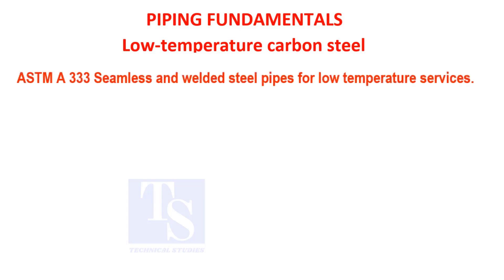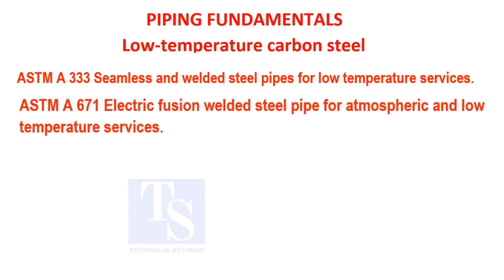ASTM A-691: carbon and alloy steel pipe for low temperature services. ASTM A-671: electric fusion welded steel pipe for atmospheric and low temperature services. Available sizes are larger than 16 inches.